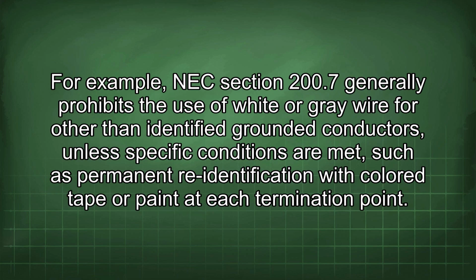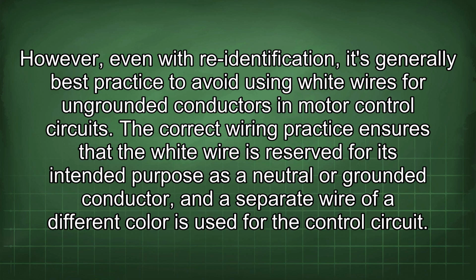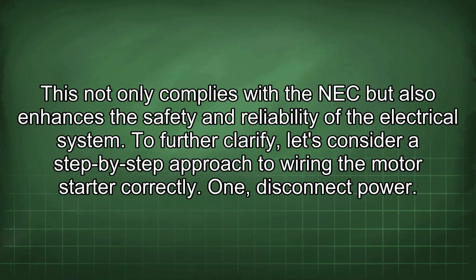For example, NEC Section 200.7 generally prohibits the use of white or grey wire for other than identified grounded conductors, unless specific conditions are met, such as permanent re-identification with colored tape or paint at each termination point. However, even with re-identification, it's generally best practice to avoid using white wires for ungrounded conductors in motor control circuits. The correct wiring practice ensures that the white wire is reserved for its intended purpose as a neutral or grounded conductor, and a separate wire of a different color is used for the control circuit. This not only complies with the NEC but also enhances the safety and reliability of the electrical system.